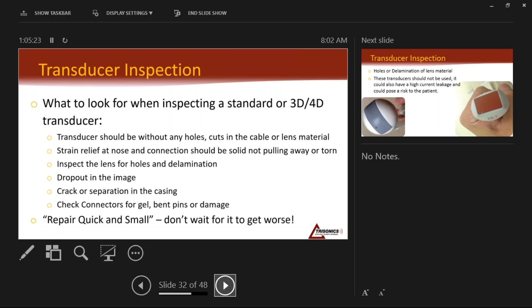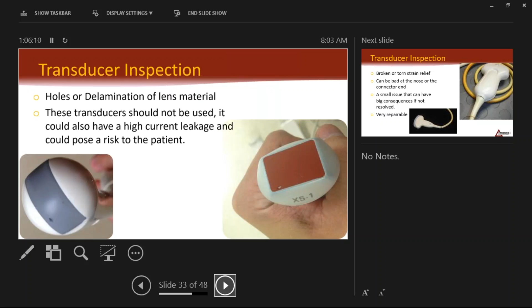So, just a few examples of some holes. Not only are these holes, now the transducer is leaking more current than it's allowed to. Generally, if there's a hole in the lens, we're also leaking more current. So it's failing safety. We tell sonographers all the time, if your patient talks about the probe tickling or they feel like it's pulling hairs on their skin, they are probably getting shocked. That is something that happens. So every PM, transducer safety should be done now. All the manufacturers do it, and because we have to do the same PM as them, now we have to do it too. So something should happen.